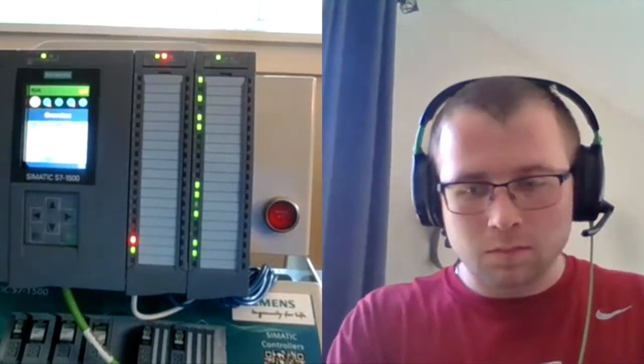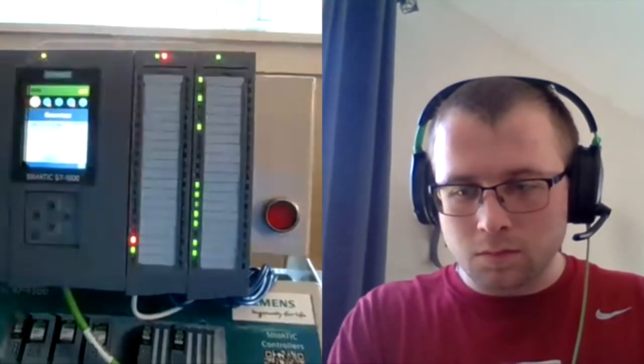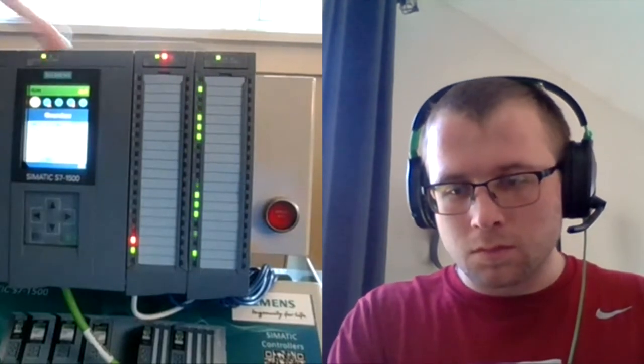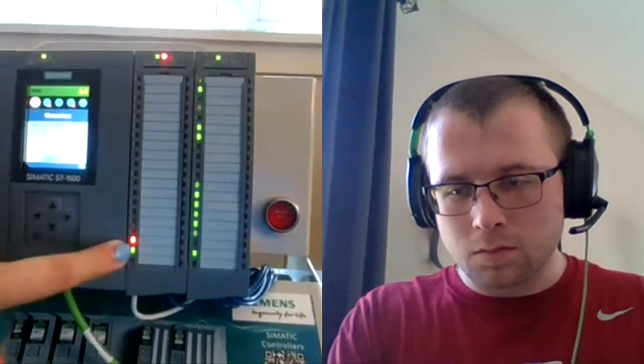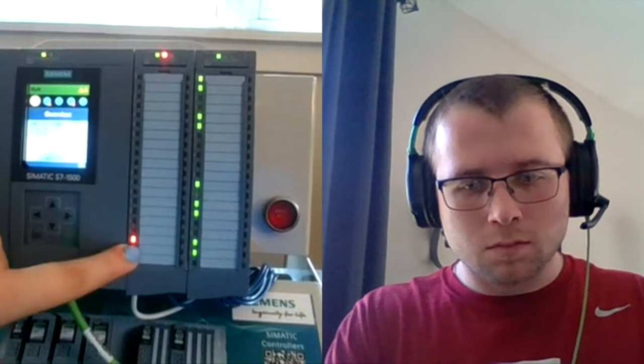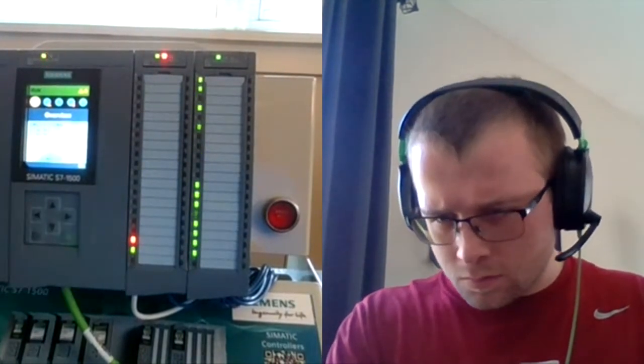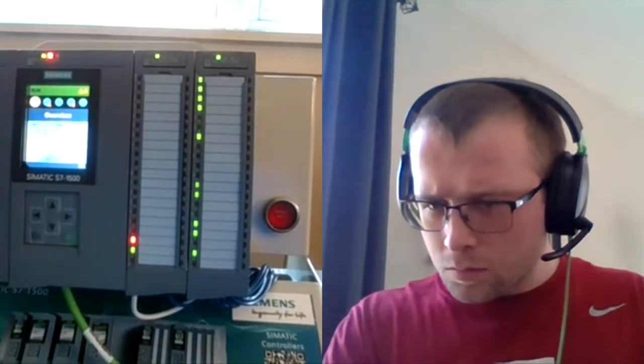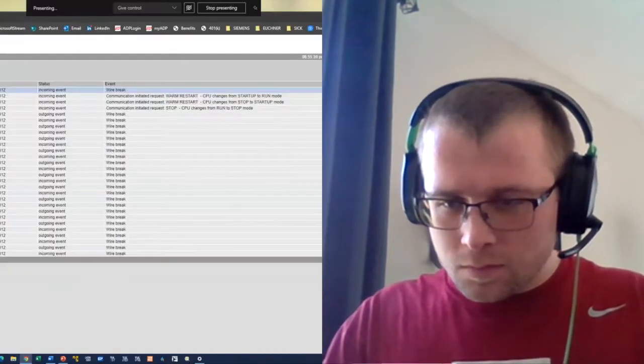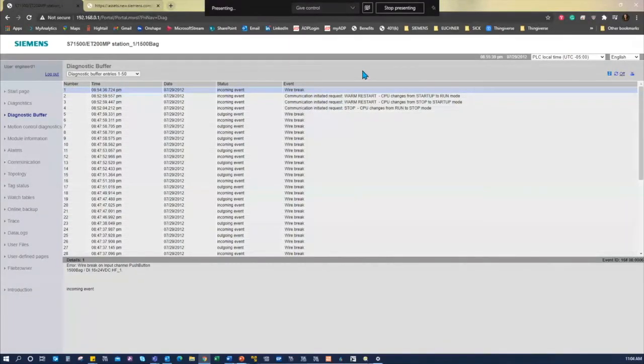I have a wire break that's simulated. I see that error on the PLC, on the I/O card, and directly at the I/O at which this error is occurring. And again, I have that on the web server as well. So you have many different places where you can get this diagnostics information from, so that you can troubleshoot a bit quicker.